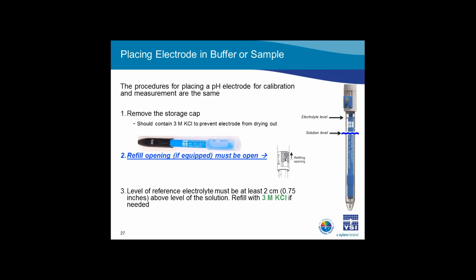The storage cap is filled with solution to keep the electrode from drying out and to slow the outflow of electrolyte. The solution used varies by manufacturer and electrode, but is usually KCl solution, buffer 4, or a mix of the two. Next, if using a refillable electrode, make sure the fill hole is open for both calibration and measurement. This is very important and a commonly missed step, especially if using a refillable electrode for the first time.